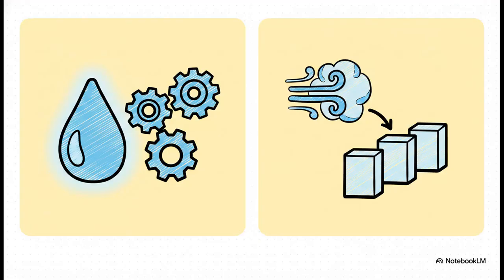So, engineers face a fundamental choice. Do you harness the supreme efficiency of water or the logistical simplicity of air? Water-cooled systems use cooling water to chill the refrigerant, and this gives them the absolute highest levels of energy efficiency, or COP. Plus, they're perfect for large-capacity facilities and are really stable against outside weather changes. Air-cooled systems, on the flip side, are completely waterless. They have a simple structure, they're incredibly fast to install, and they are significantly easier to maintain.